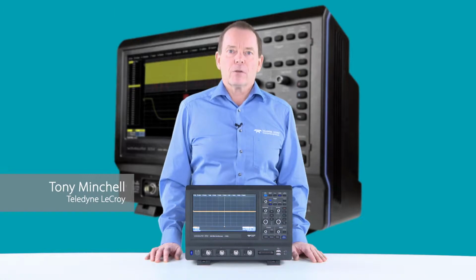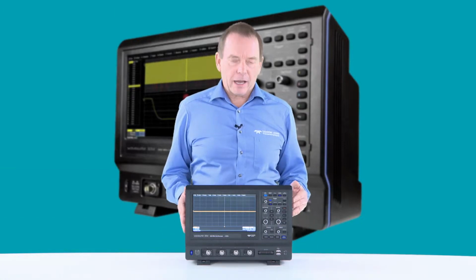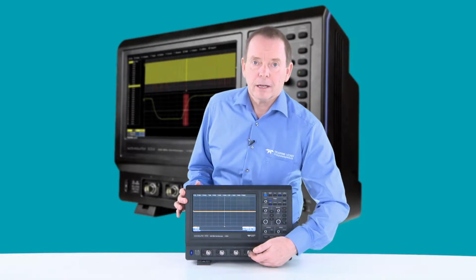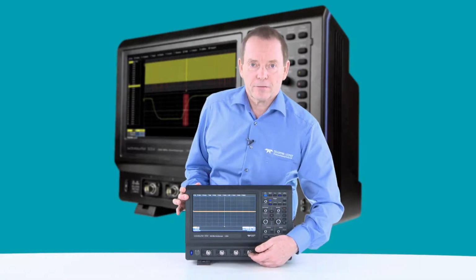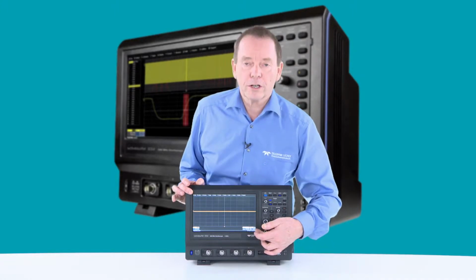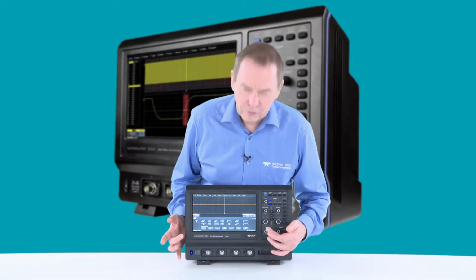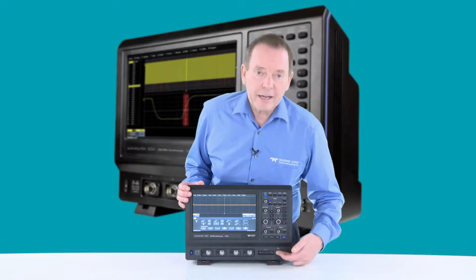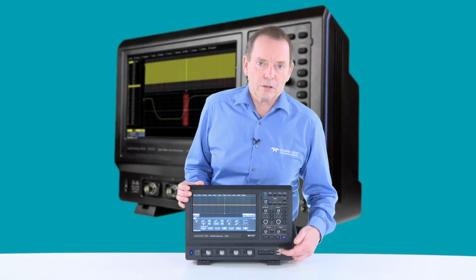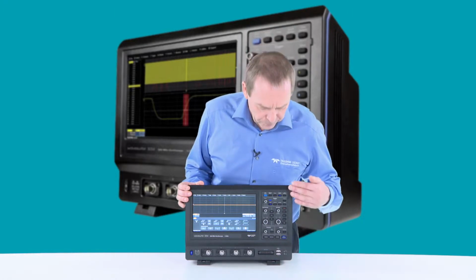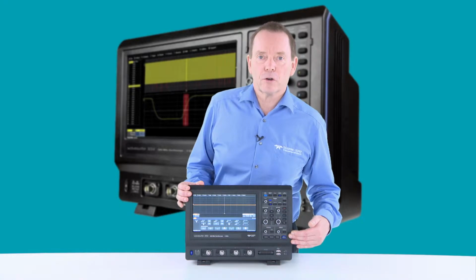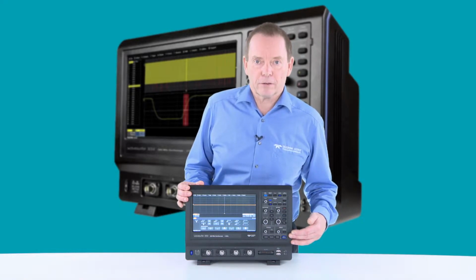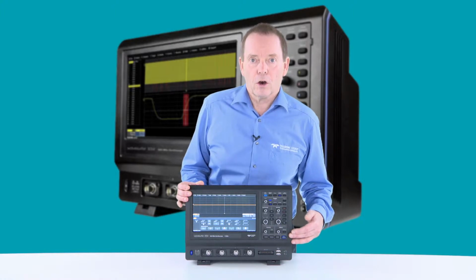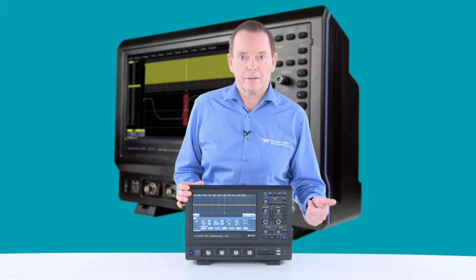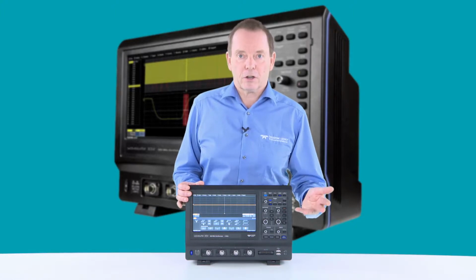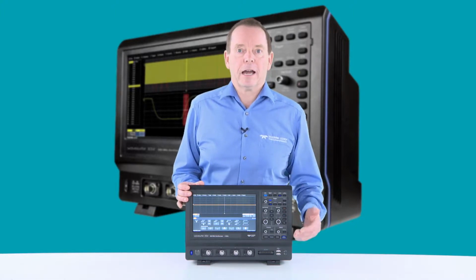I want to talk to you today about the WaveSurfer 3000. It's available in four channel models or two channel with bandwidths from 200 MHz to 750 MHz. It's got a 10.1 inch touchscreen, so I can pop up my menus. It also has a connector for adding digital channels. This is optional and gives you an optional 16 digital channels. I also have an overlay here which I can use for controlling the time base and the sensitivity of the channels. The WaveSurfer 3000 also has advanced triggering, advanced math, measurements, statistics, histograms and other capabilities built in as standard.